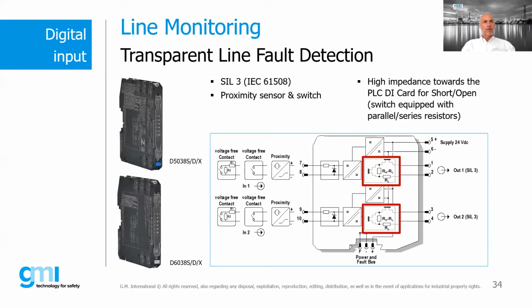Massimo, can you say something about the fault detection? Yes, Andrea, yes. Thank you. GMI has developed two particular digital input models, SIL2 and SIL3, capable of transparently transferring the status of a sensor or contact in the field to a supervised digital input card of a PLC. This allows our safety system to know exactly the state of the loop in the field.